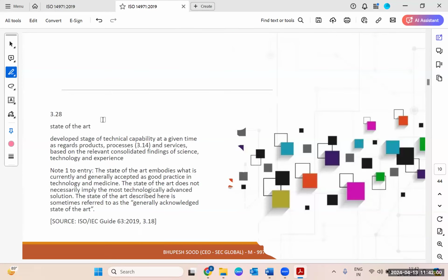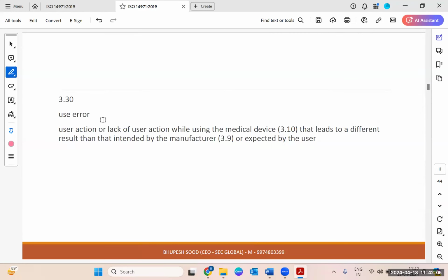Intended use of any medical device is an important aspect. This is the first fundamental that you should know and work upon. What is the intended use of a medical device? Intended use means what the medical device is basically being used for. When you're talking about risk analysis, another aspect to consider is use error. Use error means lack of action by the person using the medical device.